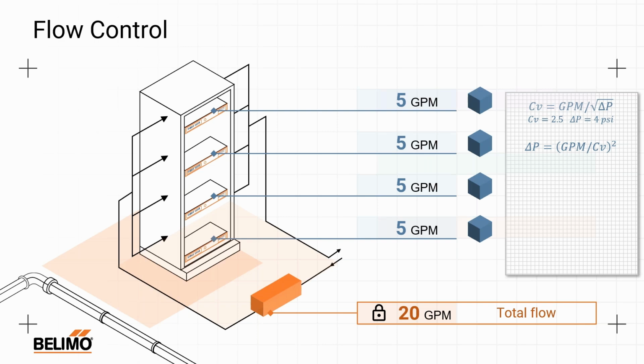For the sake of the discussion here, we're going to say each of these servers has a flow coefficient of 2.5 and the total pressure drop is 4 psi. And then we're going to take the flow coefficient formula and simply solve it for pressure drop. So you can see we have delta P equals the flow rate divided by the flow coefficient, that quantity squared. Why did we do that? Because if I have 4 servers in place, that means I have 20 gallons a minute. I have 2.5 Cv times 4 servers. That gives me 10. 20 divided by 10 squared gives me the 4 psi, and everything works the way we want it to.